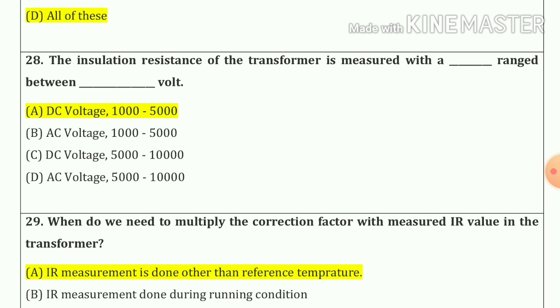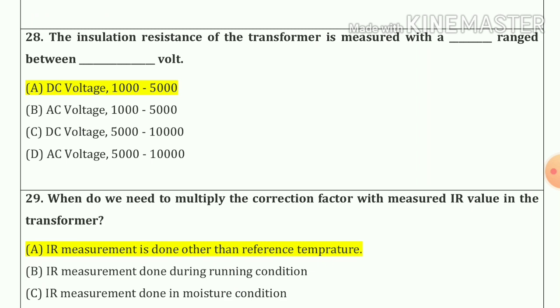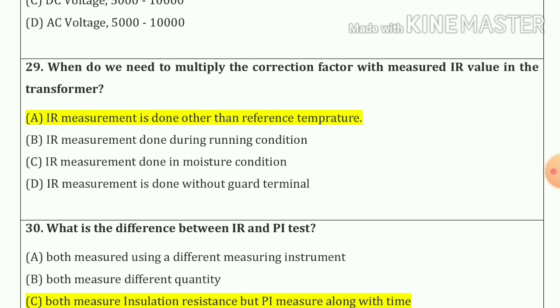Now question number 28. The insulation resistance of transformer is measured with a blank range between the blank voltage. So our answer is, the insulation resistance of transformer is measured with a DC voltage range between 1000 to 5000 volt. Question number 29. When do we need to multiply the correction factor with measured IR value in the transformer? So our answer is option number A. IR measurement is done other than reference temperature.